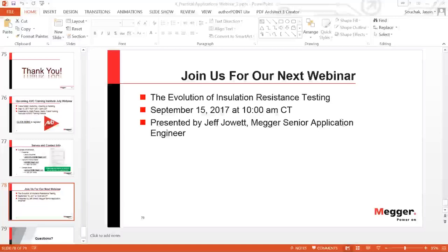All right, next question is for Jason. What is the standard value of tan delta? Okay, there's no specific standard value. That's why we have the IEEE charts, so that you can go and reference them. I'll tell you though that typically the magnitude is going to be 1 to 2 or 3 times 10 to the negative third radian.